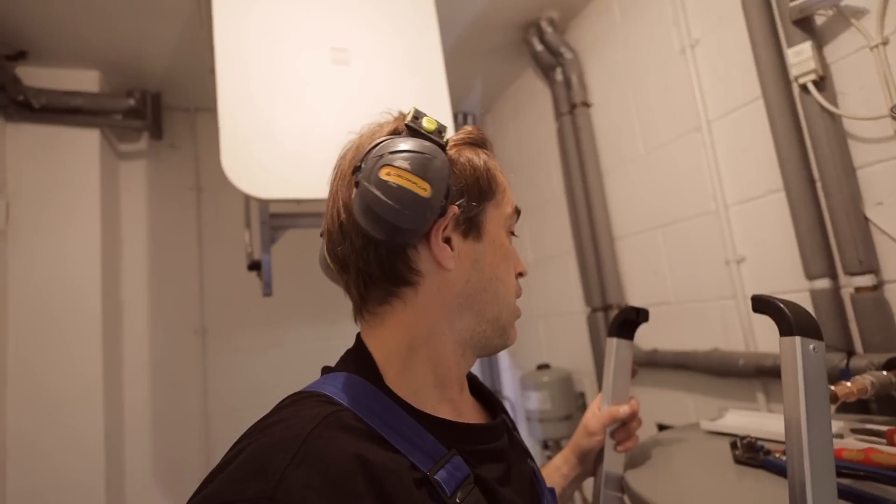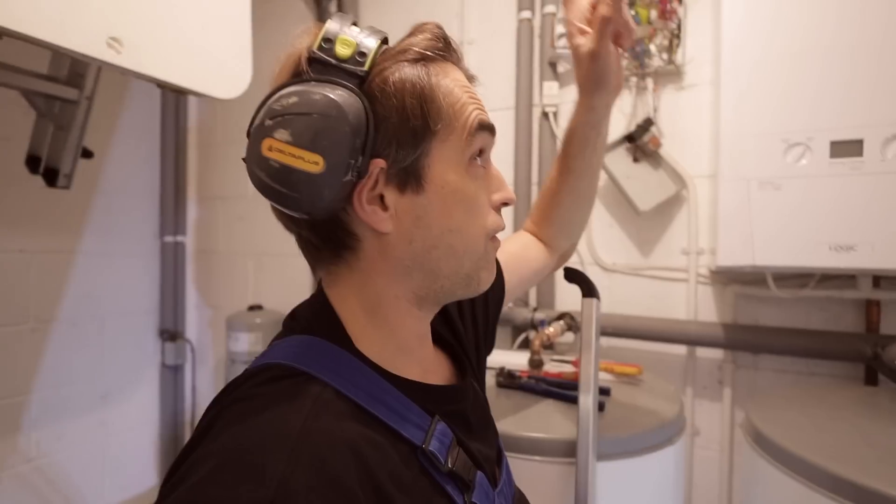This cylinder is empty, fully isolated, but it can be brought back to service if needed. I've now got two separate systems on the boilers when it comes to pipework — one small sealed system for hot water, one much larger for heating. I'm going to separate them electrically as well and install a single channel programmer to control one boiler on hot water, then run power to the programmer and the pump above on the ceiling.